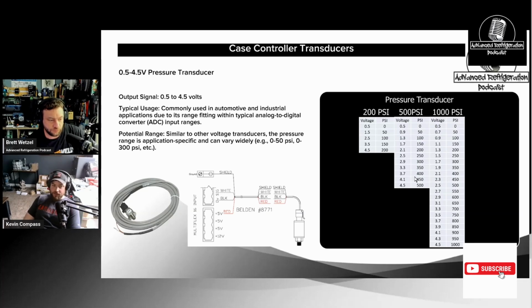If you're checking transducers with a needle gauge, you're doing it wrong. If you have an incremental gauge with increments of 1, I'm okay with that — if you can't afford digital gauges, as long as the increments work in a service truck, that's fine. Needle gauges just aren't accurate enough. I've had guys in training recently bring out their 410A gauges to check superheat or check a pressure transducer, but every increment is 5 psi — there's no way to check for accuracy with a set of 410A gauges. If you have an analog gauge with increments for every single unit, I'd trust that more if you don't have access to something like a Testo.